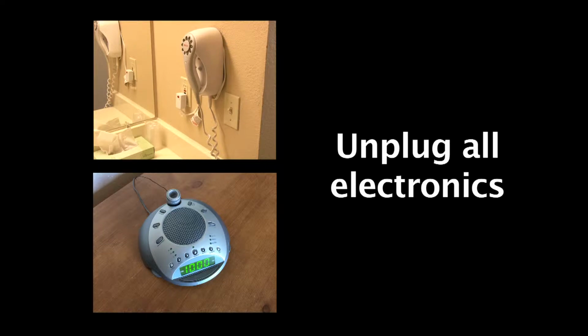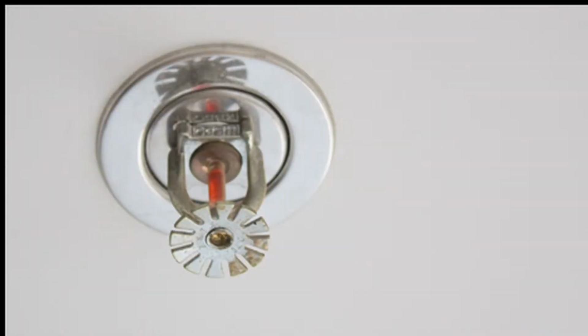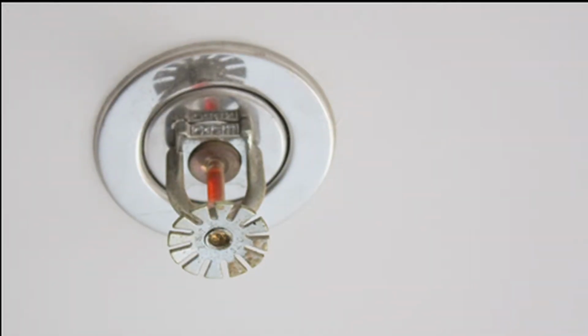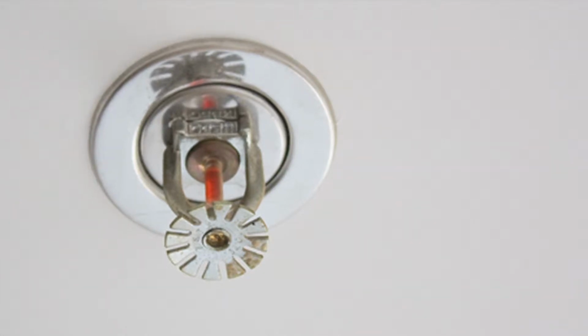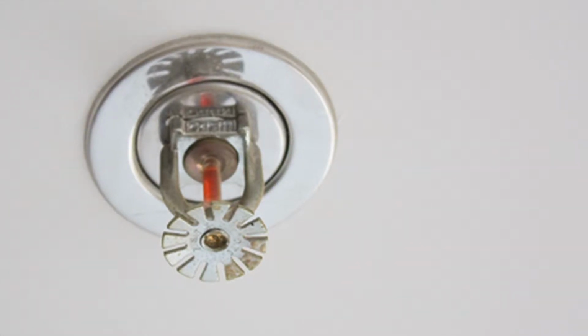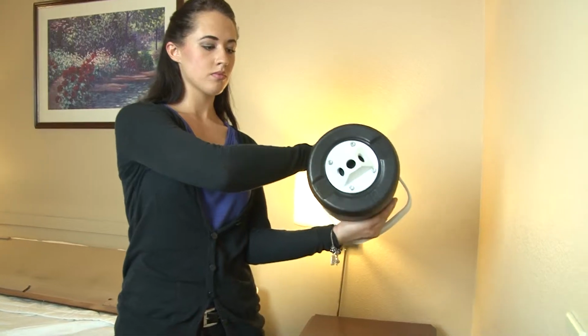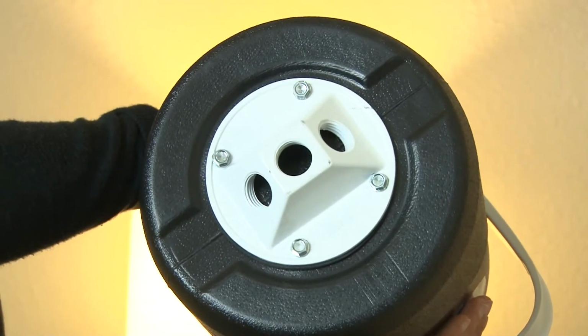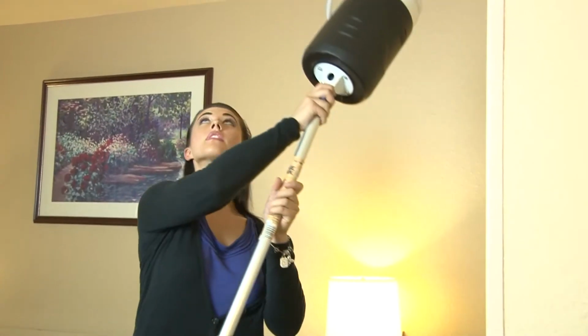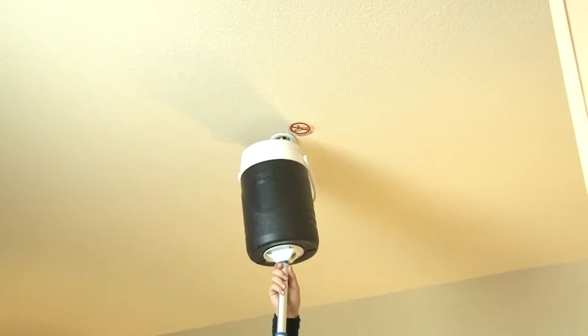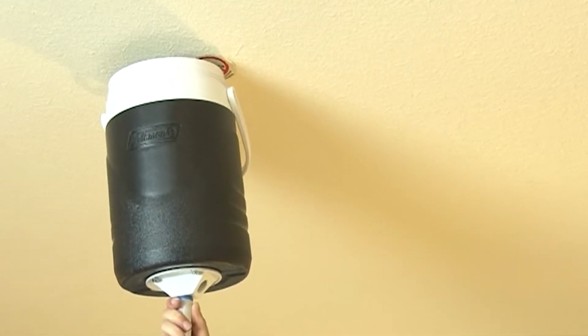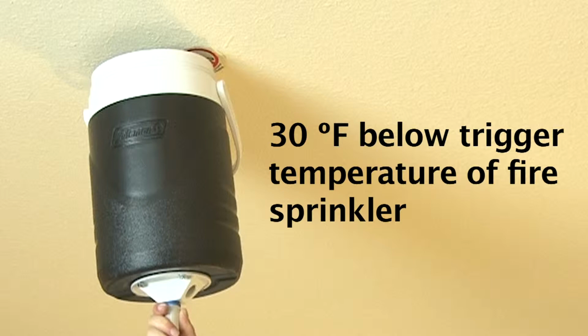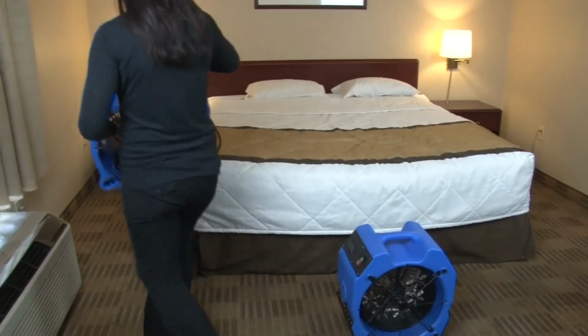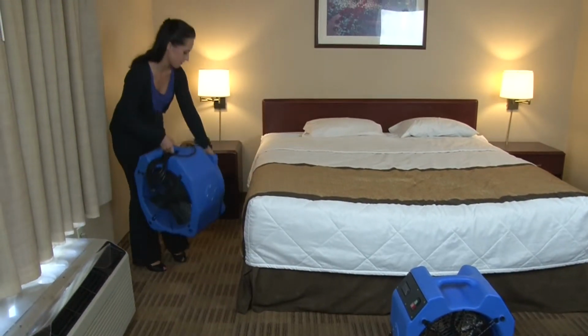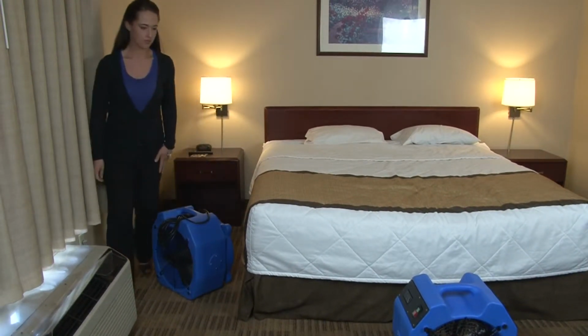Next, unplug all electronics. If your hotel has a fire sprinkler system, we recommend that the heads be drained and capped before the heat process commences. If this is not an option, we do have techniques to protect the heads in place during treatment. Always keep the heat level at the fire sprinkler head at a minimum of 30 degrees Fahrenheit below the trigger temperature of the fire sprinkler. Then, place the fans and heaters in a layout that will maximize convective air movement.